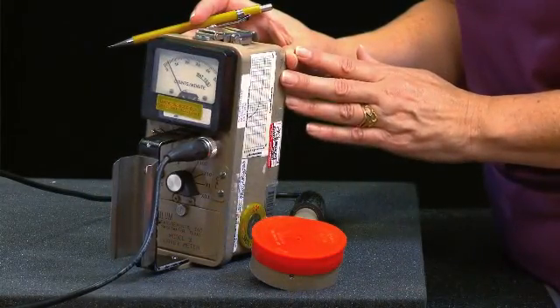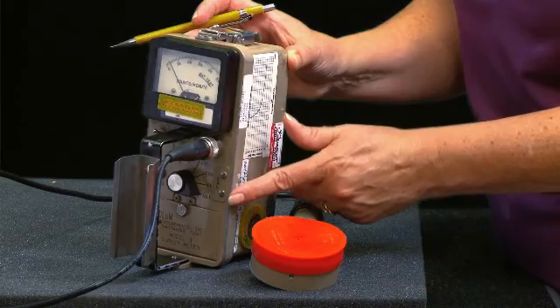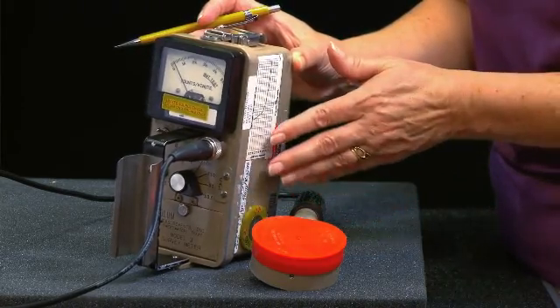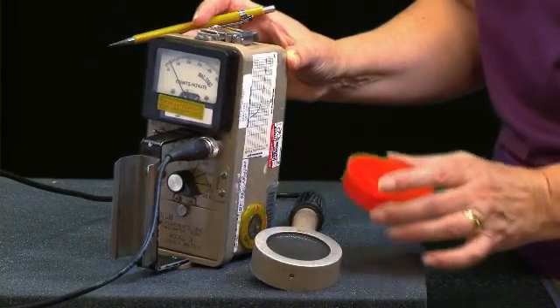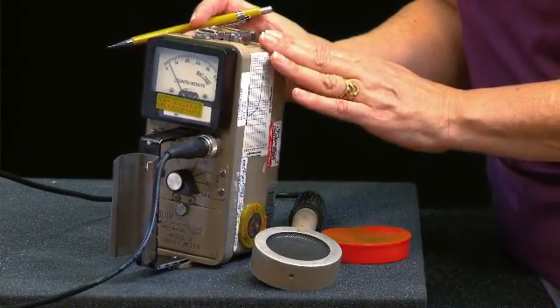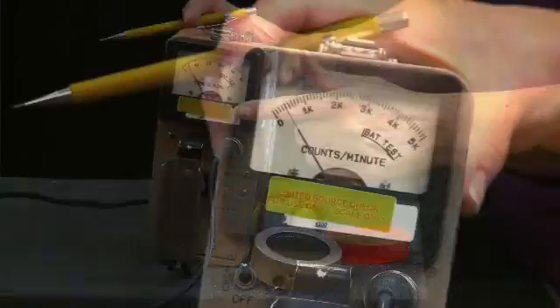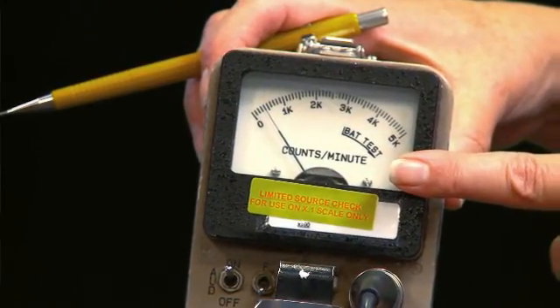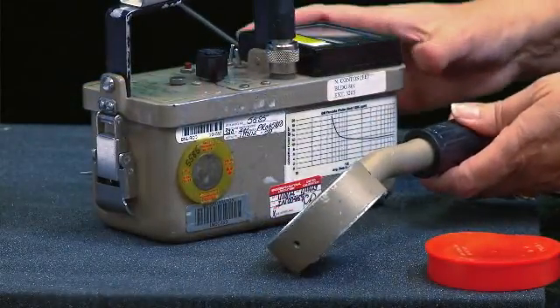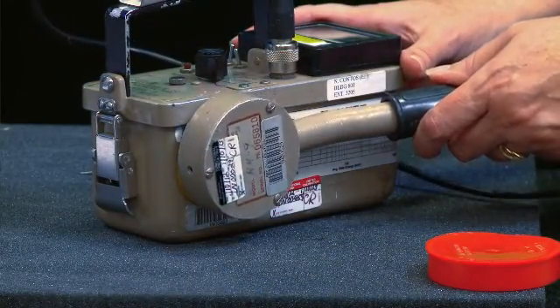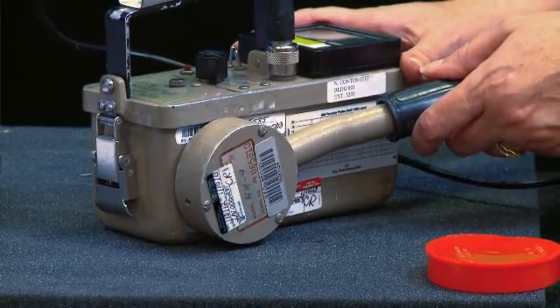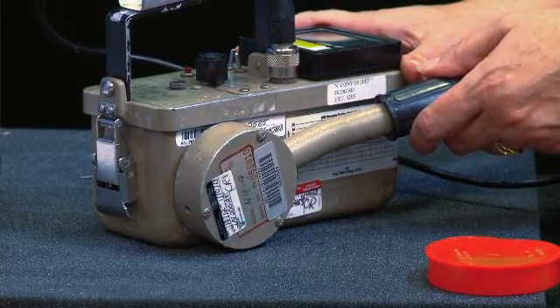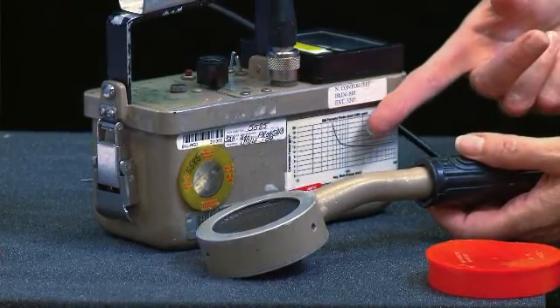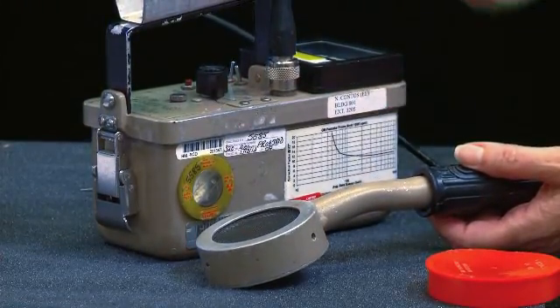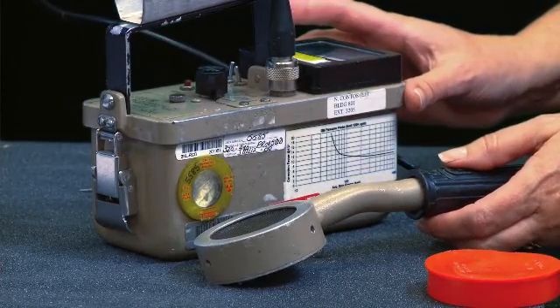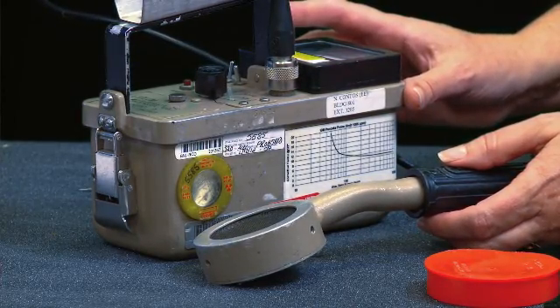Let's check the function of the meter responding to a check source. With the dial placed to 0.1 and with no radiation sources in the area, remove the red cap from the probe. Note the display and record your background level. In this case, the background is below 100 counts per minute. Place the face of the probe over the check source. A check source may be affixed to the side of the detector, or you can obtain one from your radiation safety officer. There is a label next to the check source that provides an expected response range in counts per minute. If the counts per minute displayed are within the acceptable range specified on the label, then you're good to go.